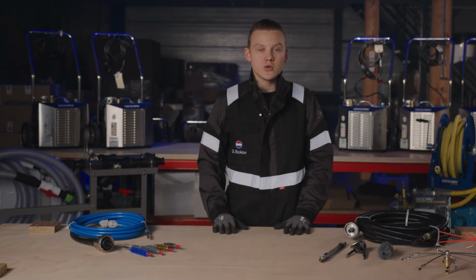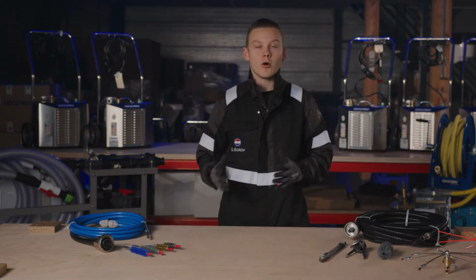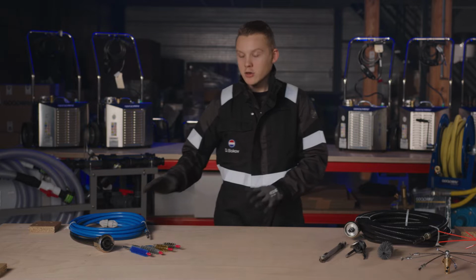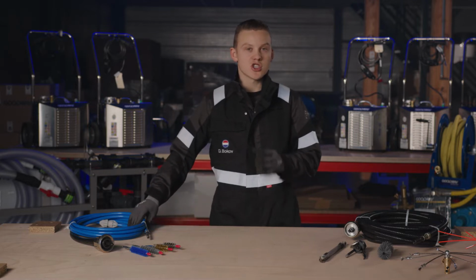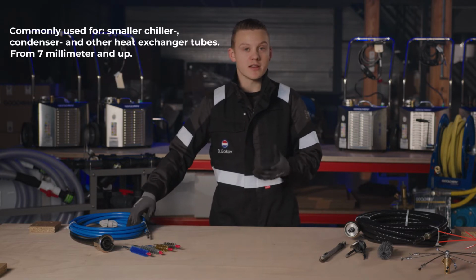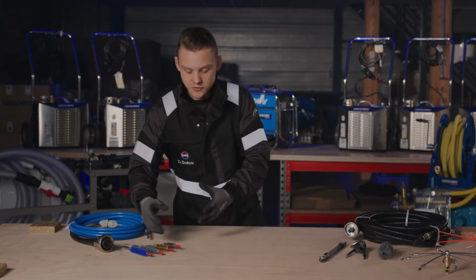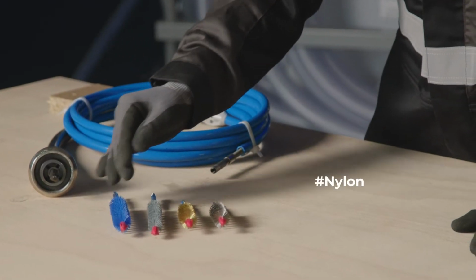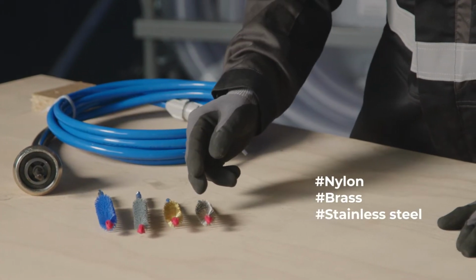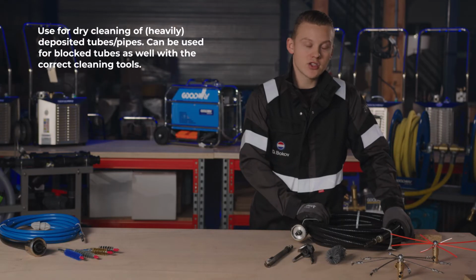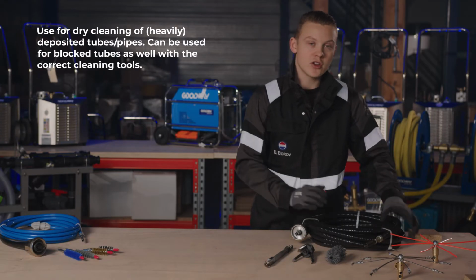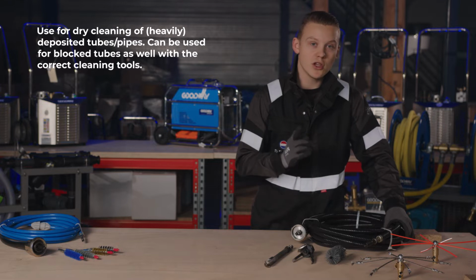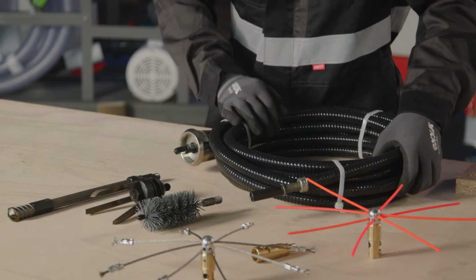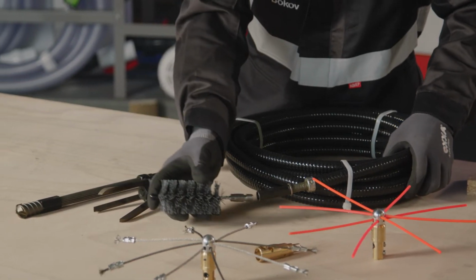Cleaning brushes and tools are essentially what make or break the cleaning. Blue flexible shafts are usually used for smaller applications such as chiller and condenser tubes. You can use various types of brushes. It can either be nylon, brass, or stainless steel. Black flexible shafts are usually used with tougher industrial tube cleaning systems which can only rotate clockwise. Hence that we always use threaded tools.